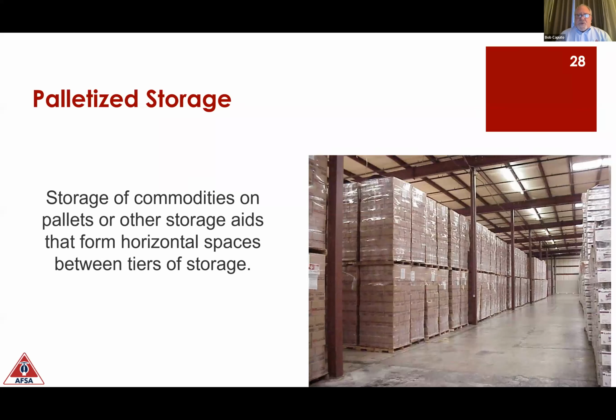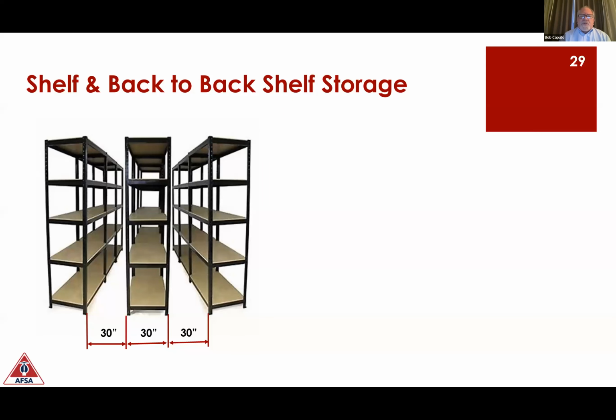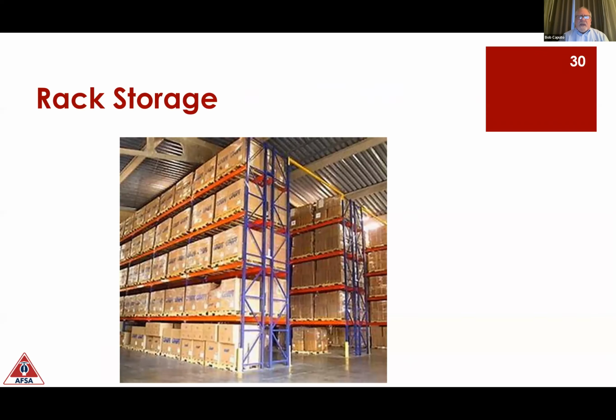This is called palletized storage. So everything's on pallets, and those pallets create a space for the forklift to come in and move the unit load. These pallets are going to form a horizontal space between the tiers of storage for the fire to travel through, if you will. But for the most part, these fires are going to be on the faces of these cartons or of these blocks of storage. This is shelf storage, usually 30 inches wide with 30-inch aisles. And again, these are solid shelves. Those 30-inch aisles are critical. Sometimes you'll see this in back-to-back.